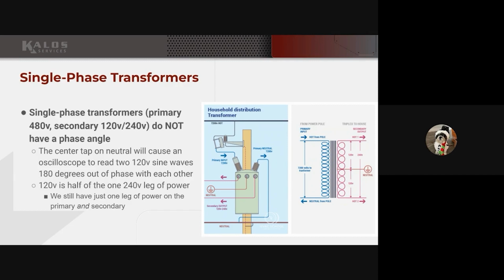So voltage drop is a common-ish reason. Sometimes, I believe in recent history, you'll get a piece of equipment that is rated for 240 volts, and the premises voltage is only 208 volts. Well, in that case, you would buck the voltage for a different reason, just to get it into the specified range of that equipment.